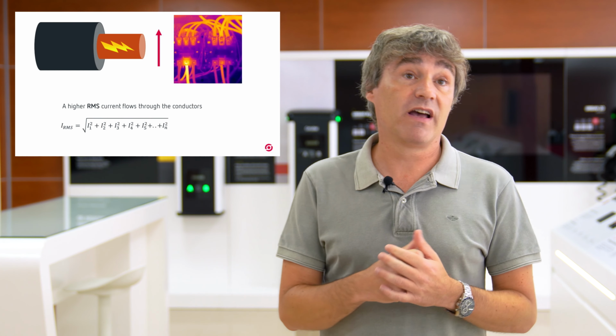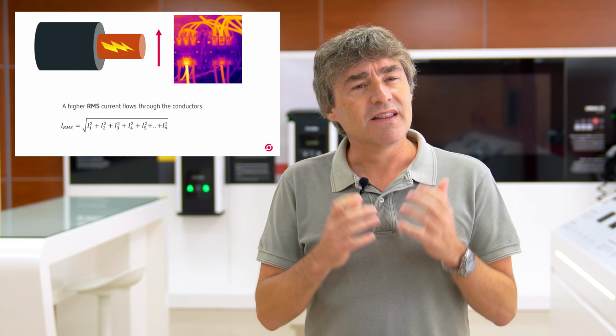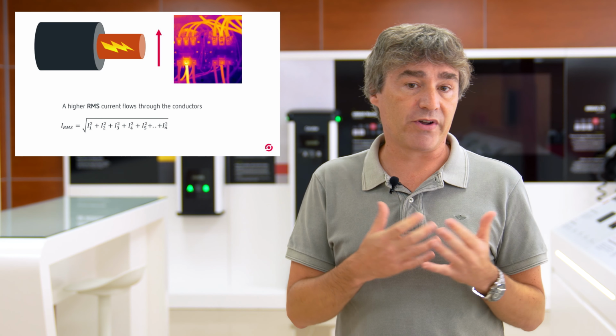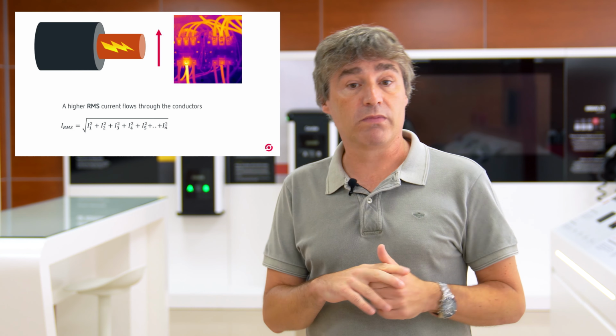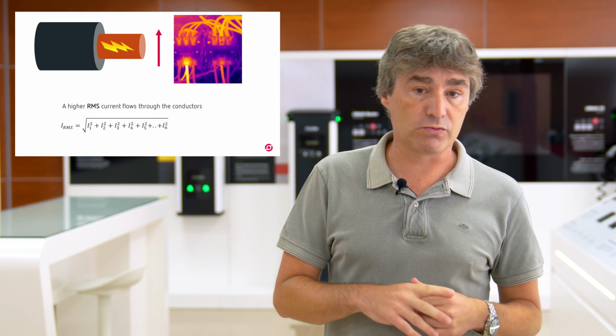Another direct effect when harmonic currents are running through the conductor is that certainly a greater RMS current, more amps, are running through them. This additional current may obviously overheat the conductors and make the overload protections trip, stopping so the operation of the downstream loads.